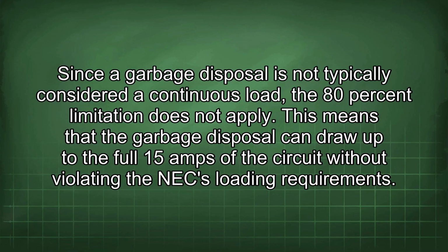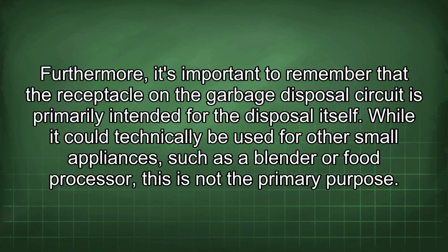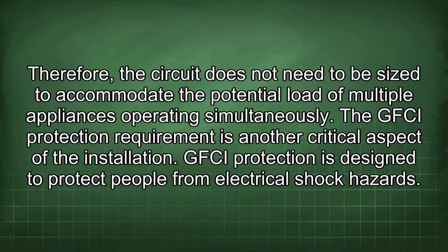NEC loading requirement. Furthermore, it's important to remember that the receptacle on the garbage disposal circuit is primarily intended for the disposal itself. While it could technically be used for other small appliances, such as a blender or food processor, this is not the primary purpose. Therefore, the circuit does not need to be sized to accommodate the potential load of multiple appliances operating simultaneously.